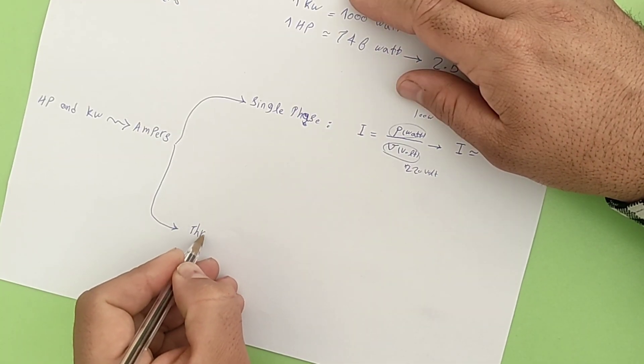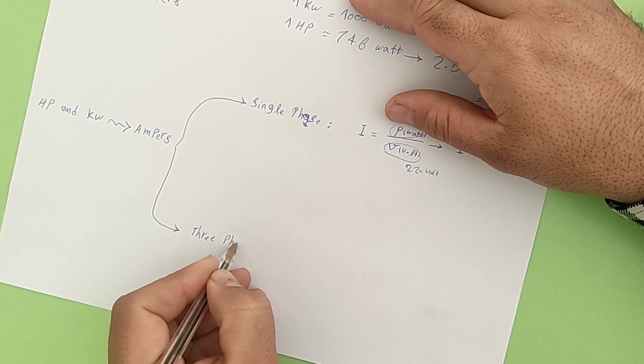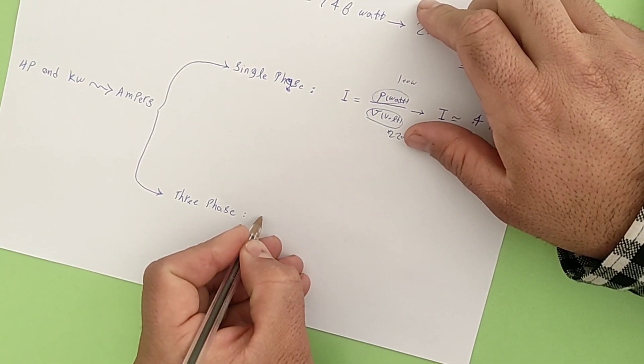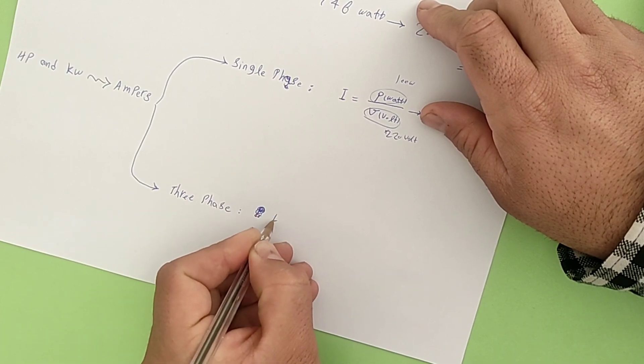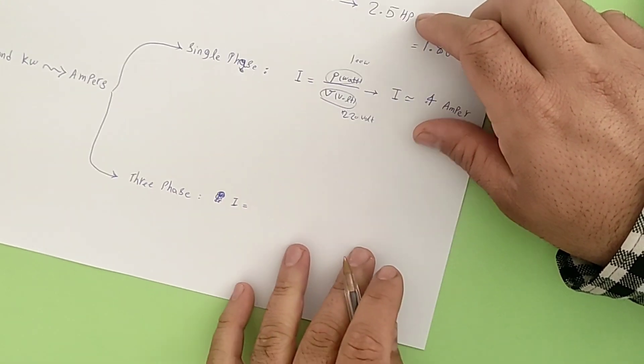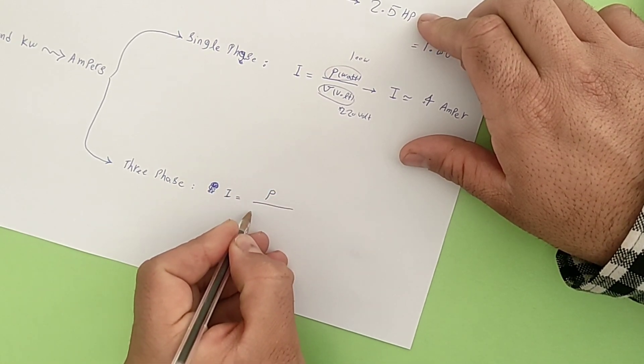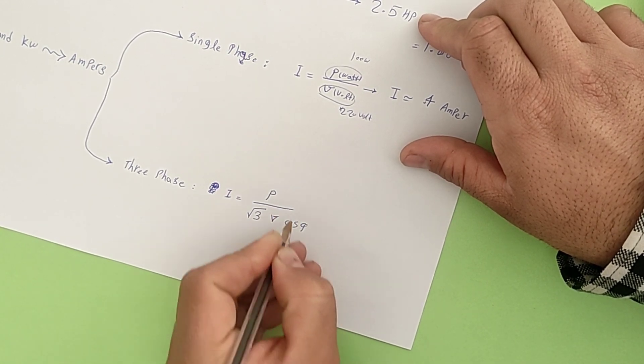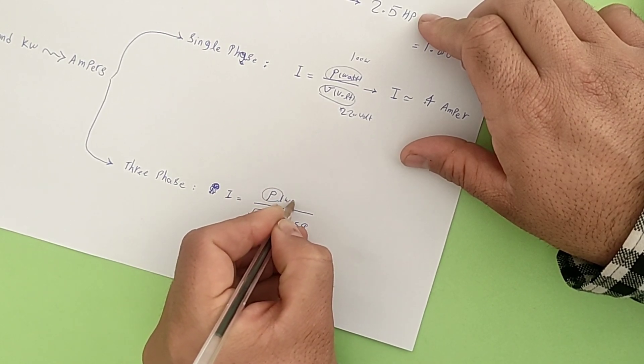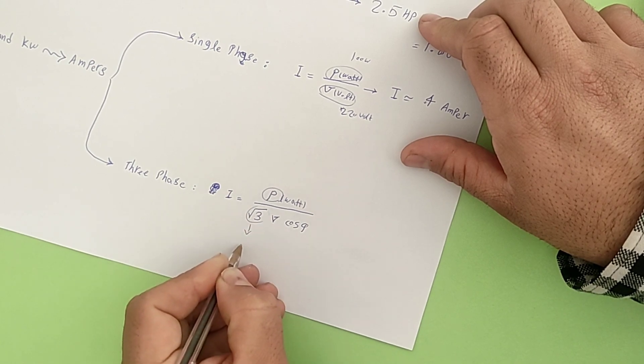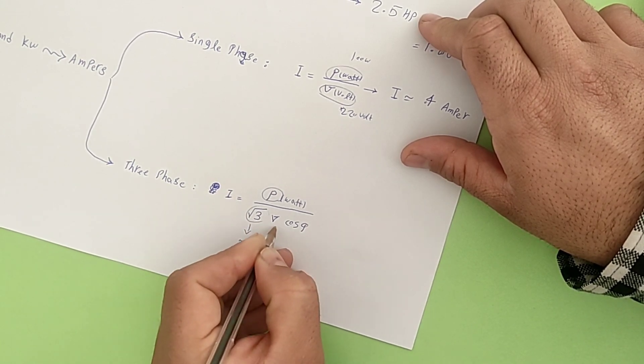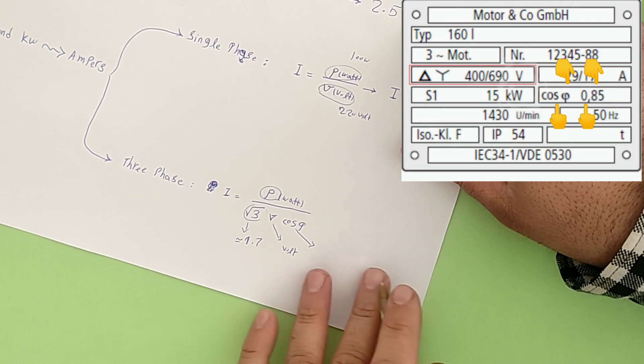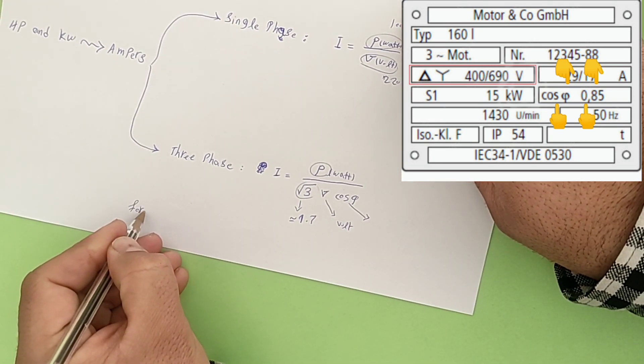Now we get the method of calculating the current in three-phase consumers. In three-phase consumers, the electric current equals the power of the consumer, written in watts, divided by the square root of three, multiplied by voltage, multiplied by cosine phi. Cosine phi is a power factor of the consumer, whose value is written on each consumer and varies between 0 and 1.